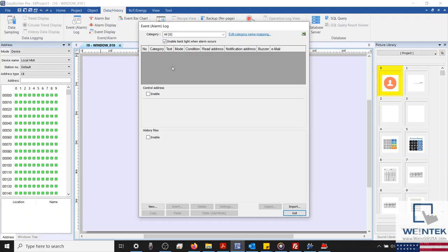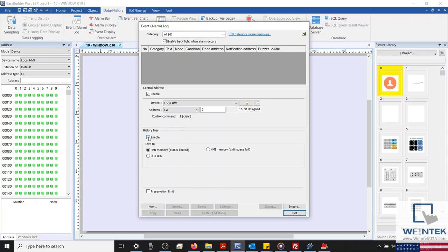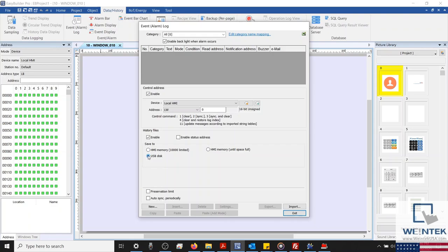Towards the center, our now gray empty field is where our list of events will populate. We can add and monitor up to 10,000 different events within EasyBuilder Pro. As with many items in EasyBuilder Pro, we can also define a control address. When not configured to send data to an external device, the control address serves but a single purpose, to clear the Event Log on the HMI. However, if we enable history files and select a directory other than the HMI, or configure the HMI to record data until the space is full, you'll notice our control commands, which are displayed under our control address, change accordingly.